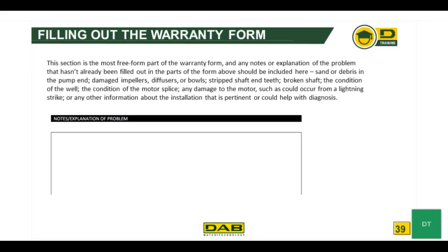Notes and explanation of problem. This section is the most free form of the warranty form, and any notes or explanation of the problem that hasn't been filled out in the parts of the form above should be included here, such as sand or debris in the pump end, damaged impellers, damaged diffusers or damaged bowls, stripped shaft end teeth, broken shaft, the condition of the well, the condition of the motor splice, any damage to the motor, such as could occur from a lightning strike, or any other information about the installation that is pertinent or could help with the diagnosis or understanding the well conditions or the warranty.